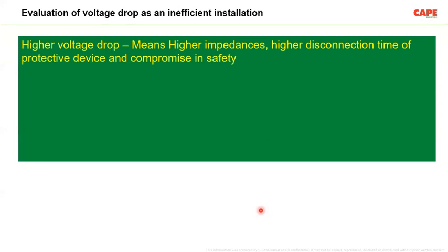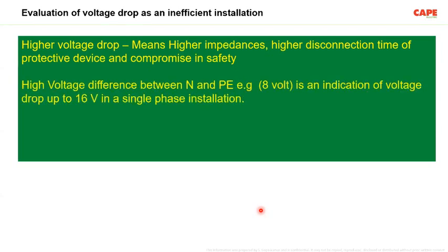Voltage drop. In a lot of cases, a higher voltage drop means a higher impedance. So if the standard says you must limit the voltage drop to 6% for lighting load, if you have your own transformer, you should not cross that. If you cross it, this means that the impedance is higher. It will lead to a higher disconnection time because the fault current or the short circuit current is less. The higher disconnection time will come into the picture and you are actually compromising safety.